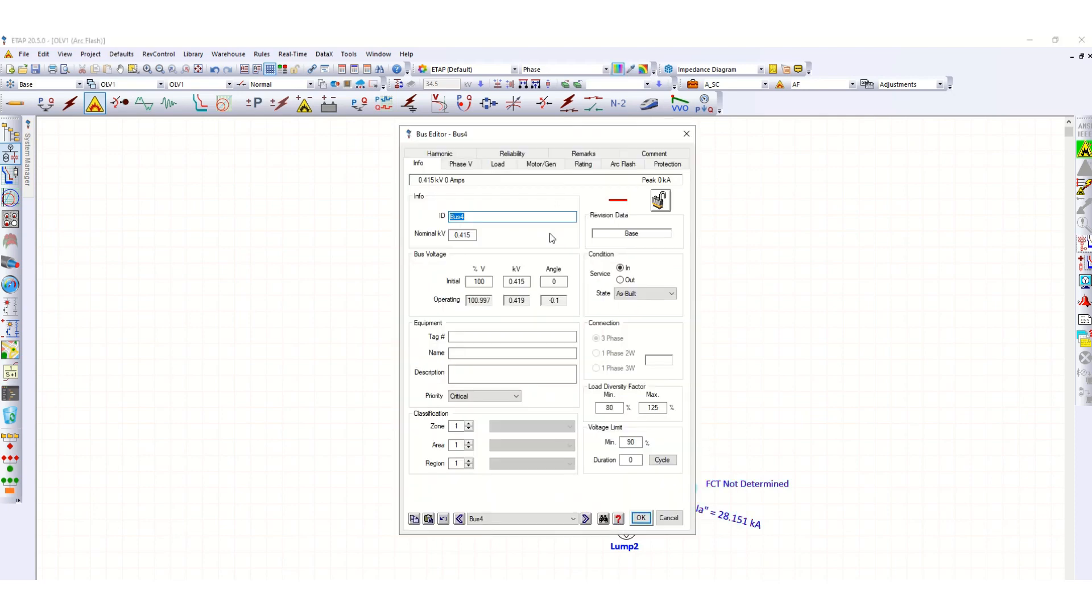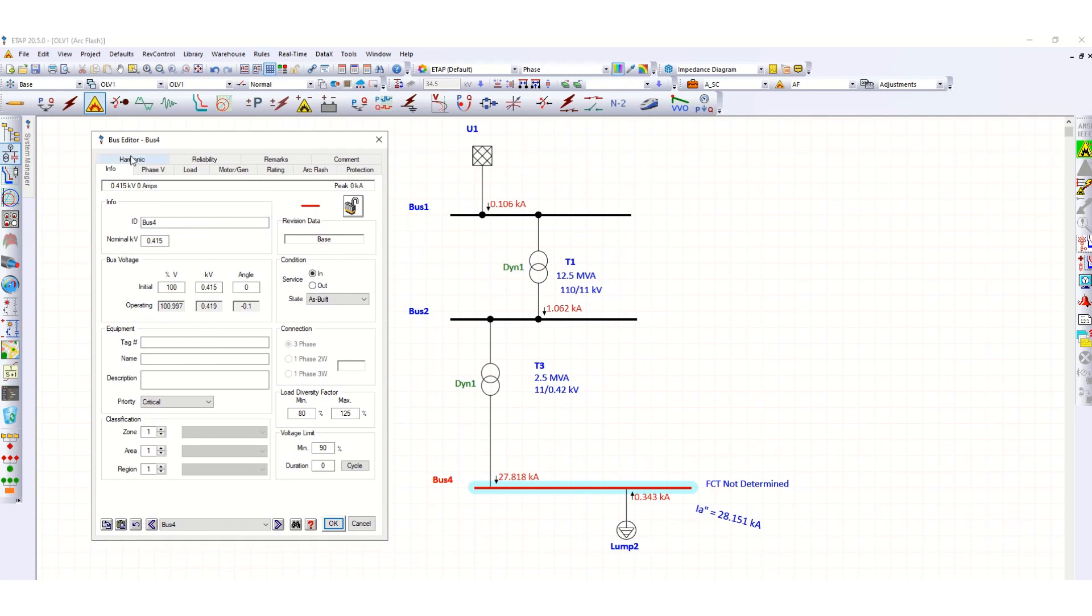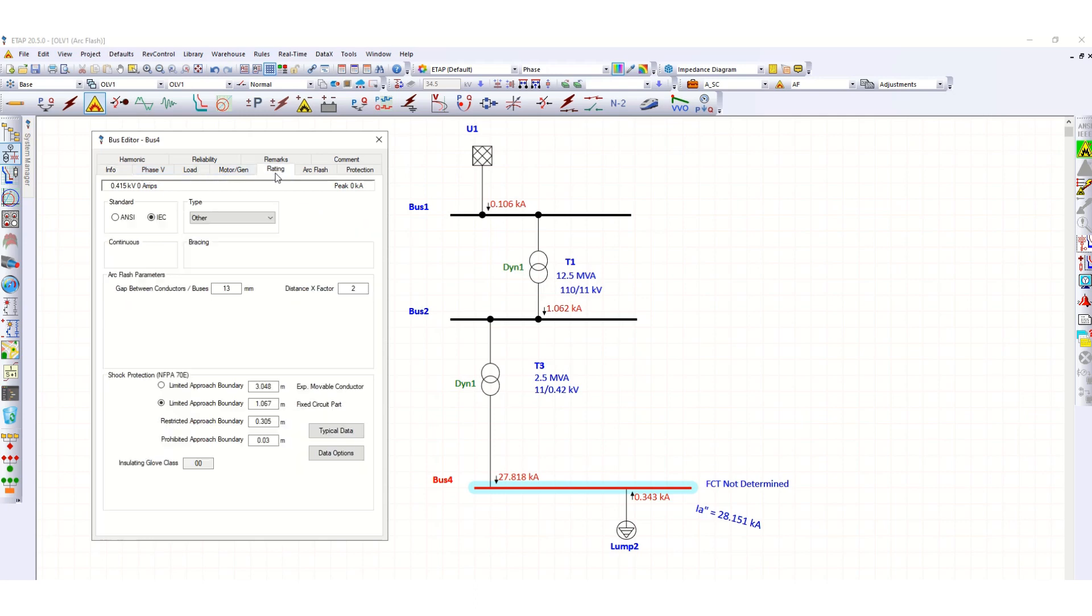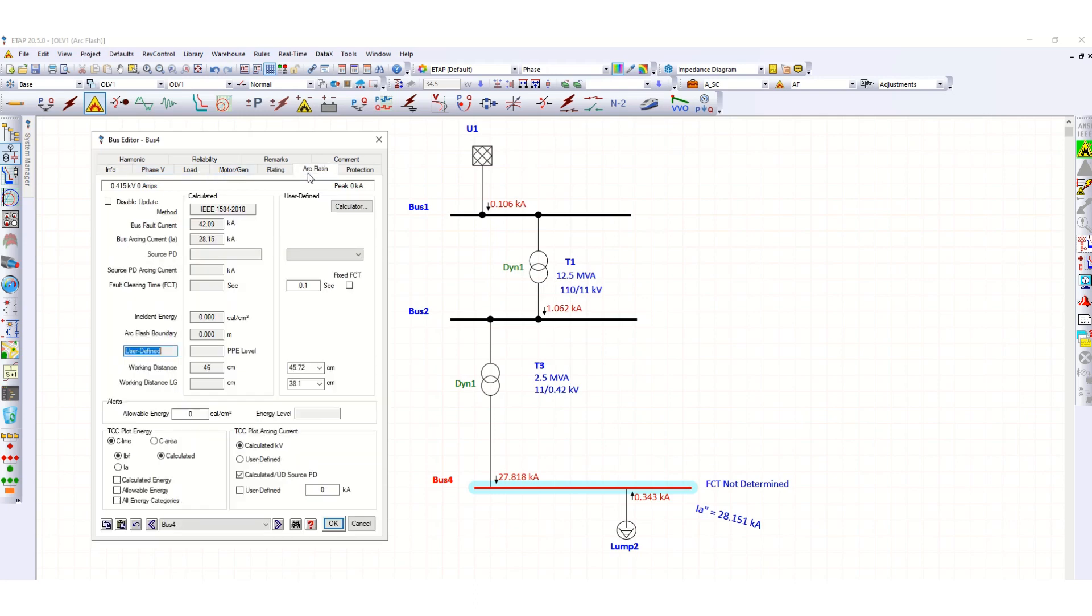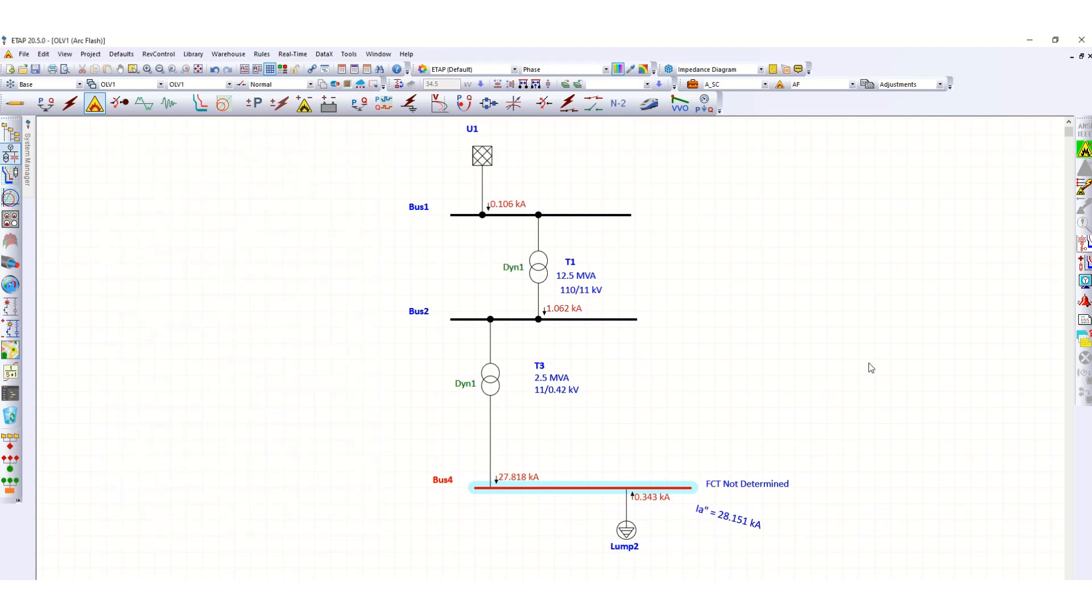Let's check in the bus editor mode under the Arc Flash tab. You can see the bus fault current and bus arcing current is 28.15 kA, but the problem is related to source PD. The source PD arcing current and fault clearing time, FCT, is not defined. That's why this error is coming. For this, we have to insert a source protective device.